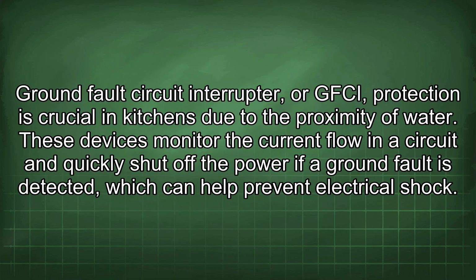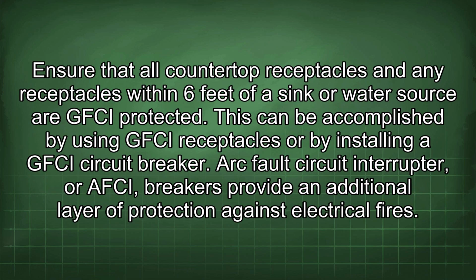Ground fault circuit interrupter, or GFCI, protection is crucial in kitchens due to the proximity of water. These devices monitor the current flow in a circuit and quickly shut off the power if a ground fault is detected, which can help prevent electrical shock. Ensure that all countertop receptacles and any receptacles within 6 feet of a sink or water source are GFCI protected. This can be accomplished by using GFCI receptacles or by installing a GFCI circuit breaker.